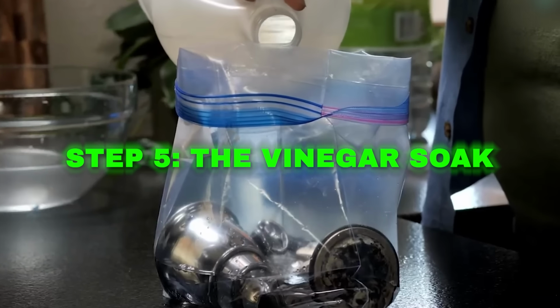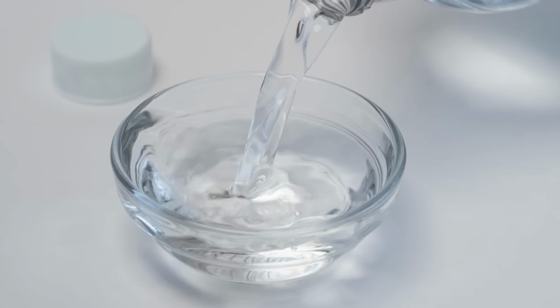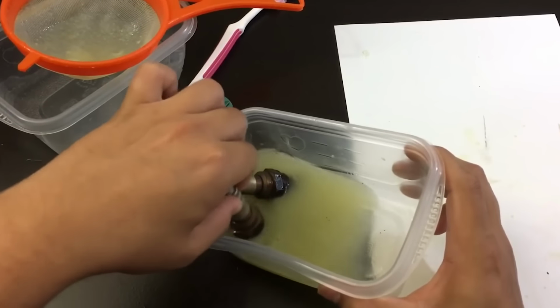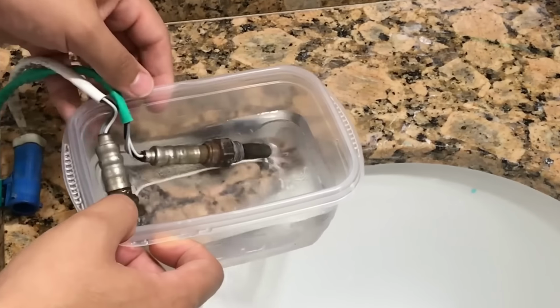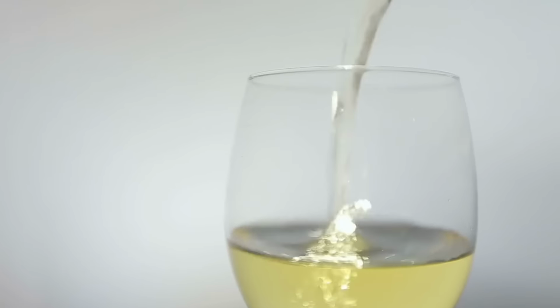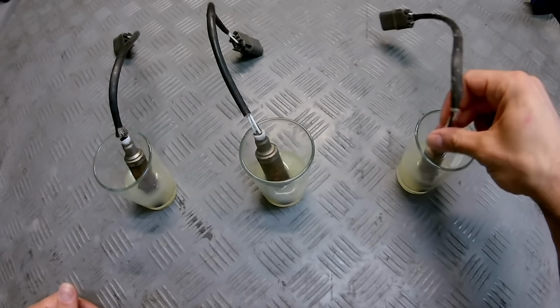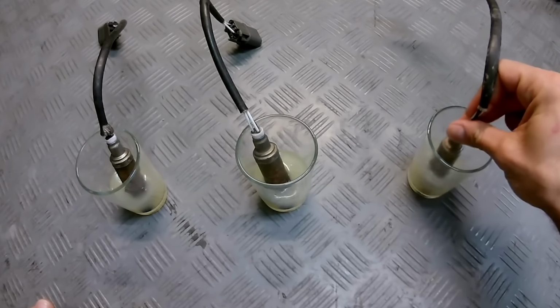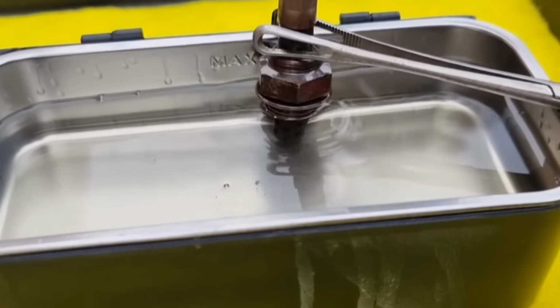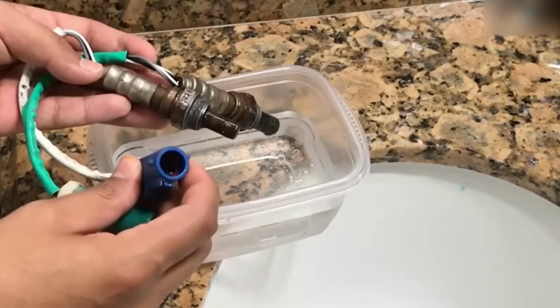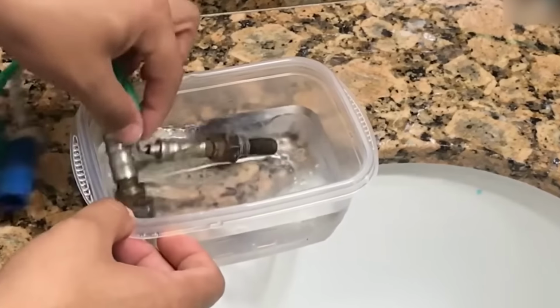Step 5. The vinegar soak. Fill your glass jar halfway with white vinegar. Submerge only the sensing element in the vinegar. The wire end and connector should stay above the liquid. Why vinegar? Because it's acetic acid, which dissolves carbon deposits and metal oxides without attacking the ceramic sensing element the way stronger solvents do. This is the Japanese mechanic's preferred cleaning agent.